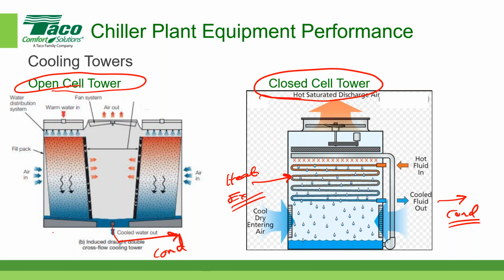What are the advantages? Well, typically for an open cell tower, you get more efficiency, but you do have the water that you have to be careful of, because ultimately the water consumption by the tower has to include not only the evaporation, but also the fact that it comes in contact with the condenser, the actual condenser.